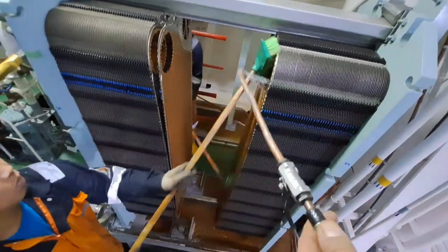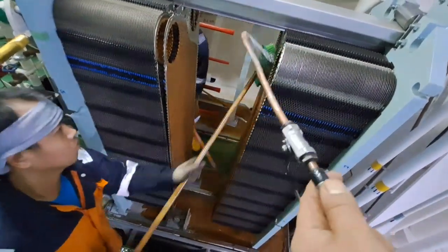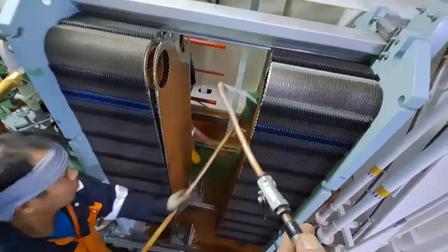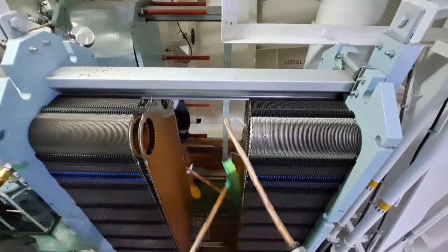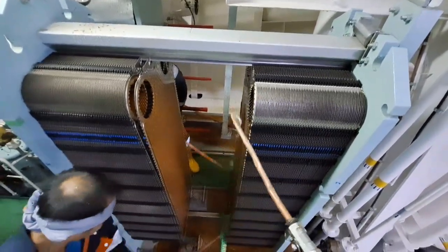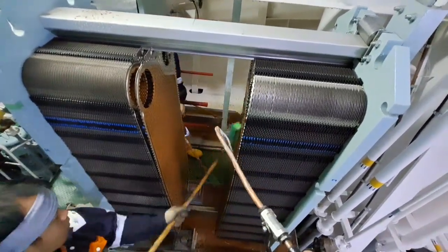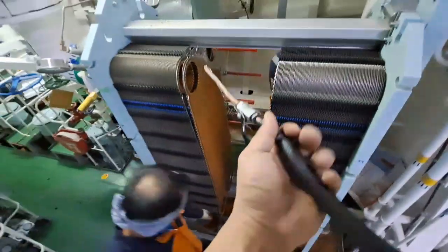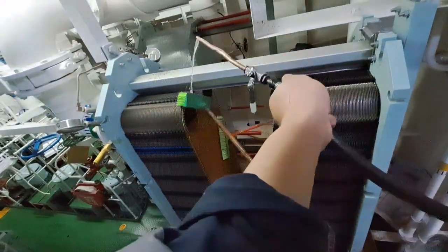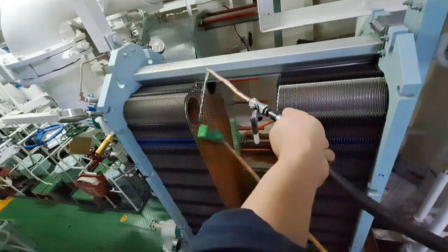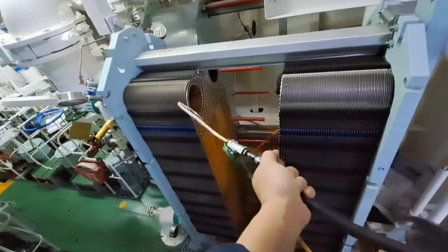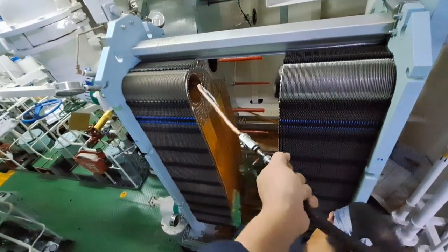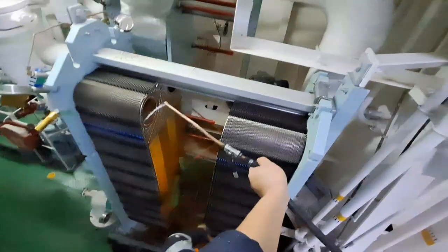This is a plate exchanger. Usually the first three symptoms are caused by plate fouling, whereas the last one is caused by gasket failure. However, any of the four can be caused by gasket failure or the rare event of plate cracks. So it's critical to take some basic procedures to figure it out.